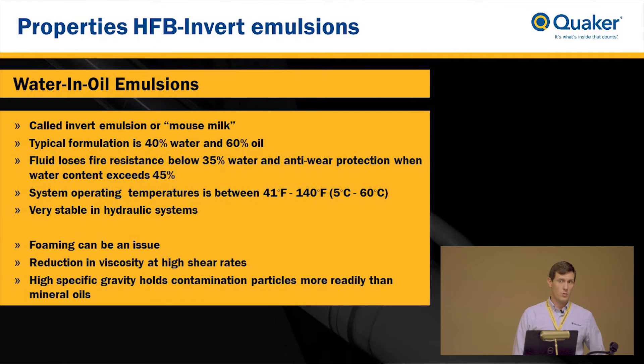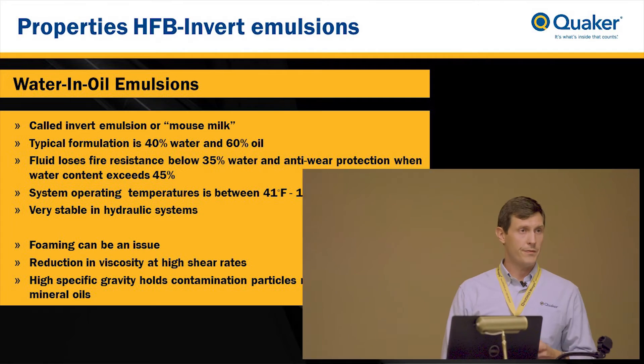These products are very stable but water content needs to be around 35 to 45 percent. If it goes under 35 percent you'll have good hydraulic fluid but fire resistant characteristics are much lower. If you go above 45 percent you have great fire resistant properties but hydraulic performance and anti-wear characteristics are lower. It's very similar to other emulsions in operating temperatures. If it starts to evaporate out you see better hydraulic performance but lower fire resistance. Issues include foaming and reduction in viscosity, and it can hold more contaminants than other types of products.